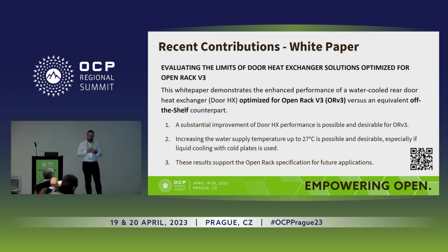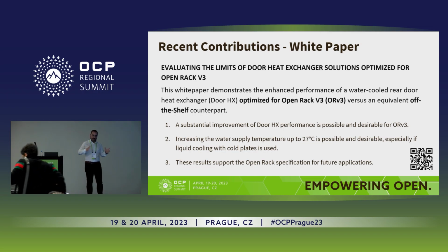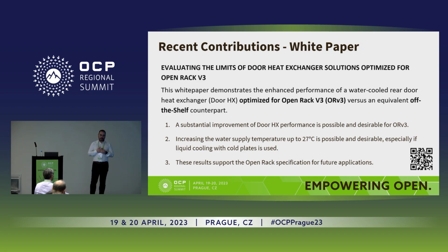And this white paper shows that it's possible, by increasing the size of the heat exchanger, to increase the performance and to increase as well the water temperature to 27 degrees. At the same time, we deploy 30 kilowatts per rack and so on.